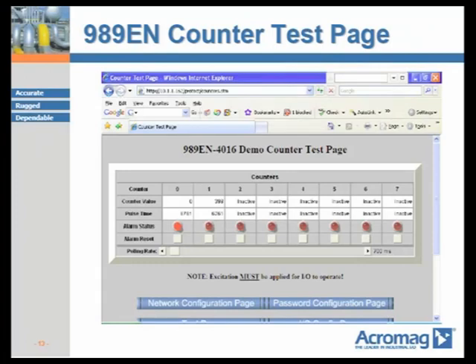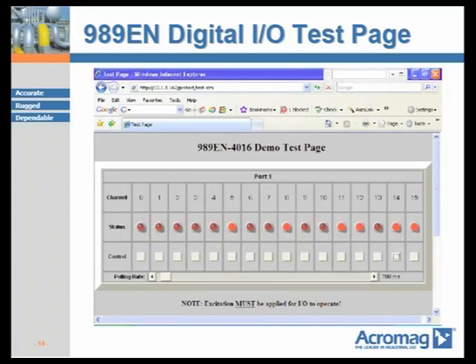All Acromag Ethernet I/O products include a built-in test page for easy checkout after configuration. The counter test page for the 989EN-4016 displays count and pulse time values for each of the first 8 channels in white boxes. If alarms are enabled, the LED indicators will actuate, and a manual push button on each channel allows the user to reset latched alarms. A slide bar at the bottom adjusts the polling and update rate from the module. The digital I/O test page is similar: discrete inputs show on-off feedback via channel LEDs, and output channels can be controlled with push buttons. These units also have built-in read-back capability for high-reliability applications.